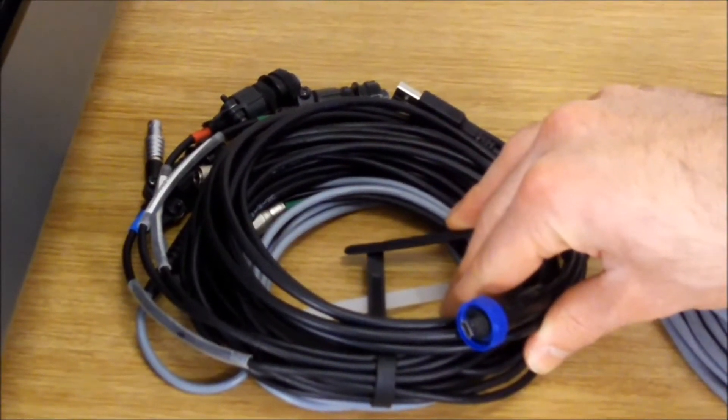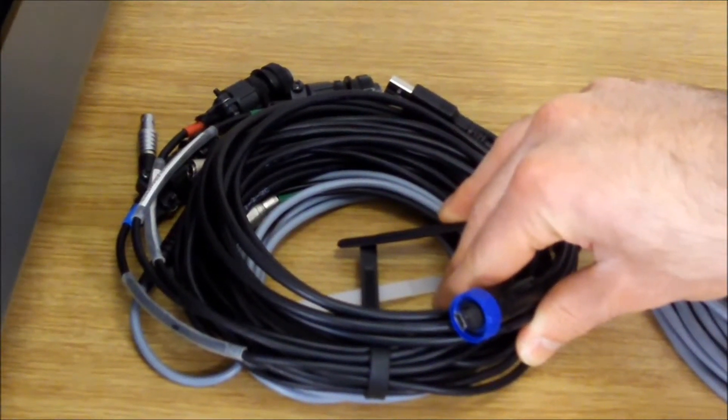These sensors come with all the required cables needed to set up the SC11SI system. So, you've got all the kit but before you perform a survey, set up the SC11SI system to perform a self-test. This is to make sure that all the sensors are connected properly and are working before used to make an accurate survey of an environment.